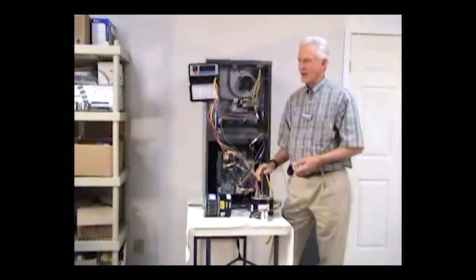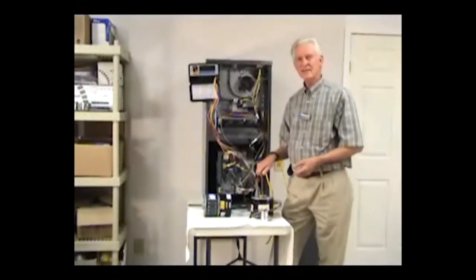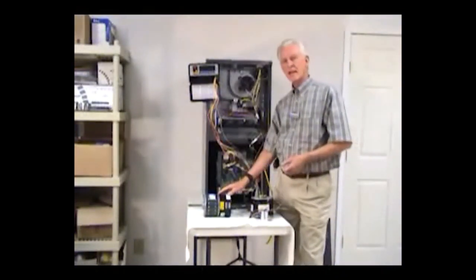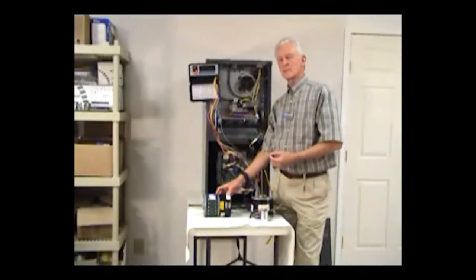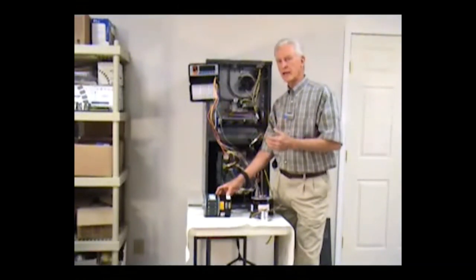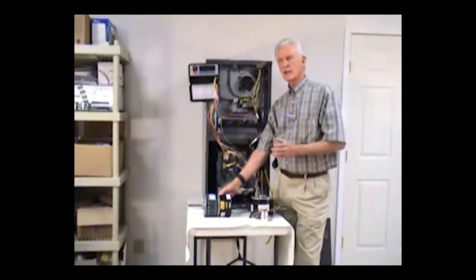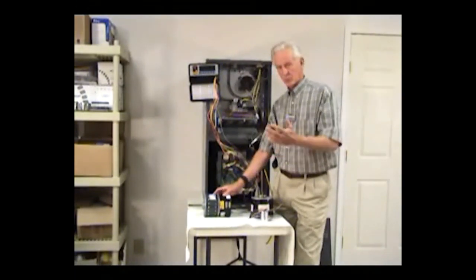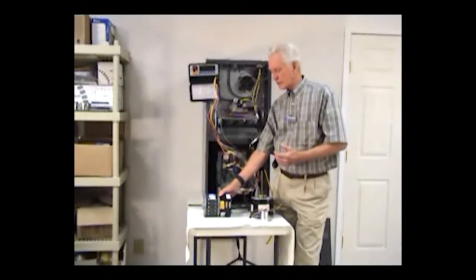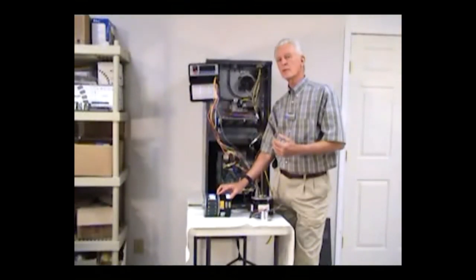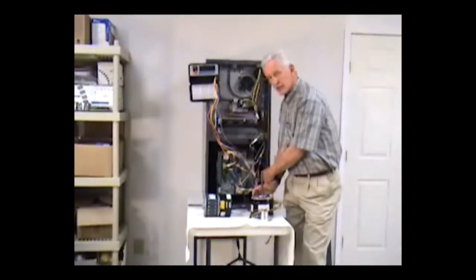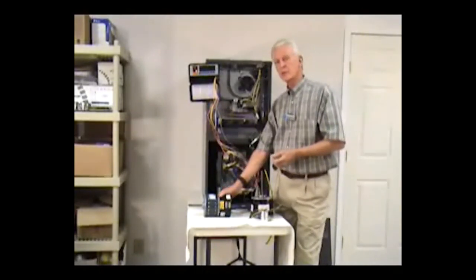Original models that they came out with, the drip legs that they had on those was one of the things that they instantly found out because of moisture. They had to make sure that the wiring arrangement of these motors was such that when they were installed, either upflow, downflow, horizontal application, the water was tracked away from the motor because there were condensation issues with the motors. Those issues have pretty much taken a back seat now because of the technology that they currently are using, they have gotten away from any of the problems that were being incurred with the water situations on those earlier models. Pretty much on the 2.0s, we had some of that, and then some of those that were before then, the ones that were attached to the side here, very little trouble with those. But the water problems have pretty much been resolved.